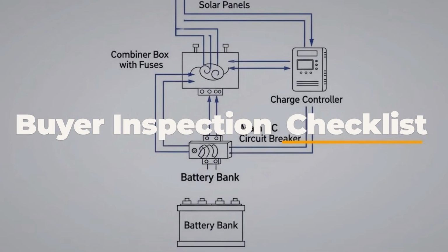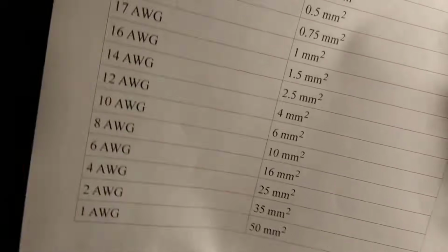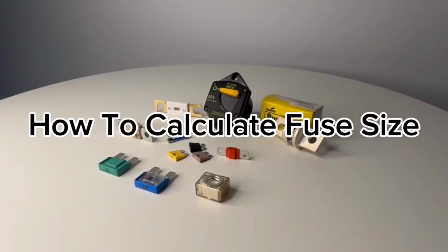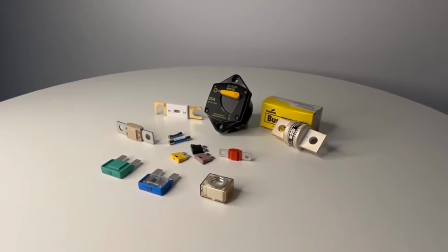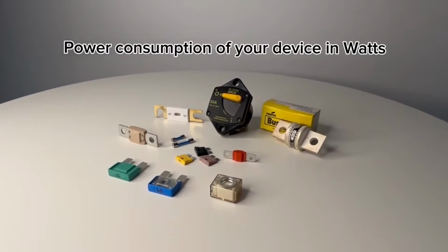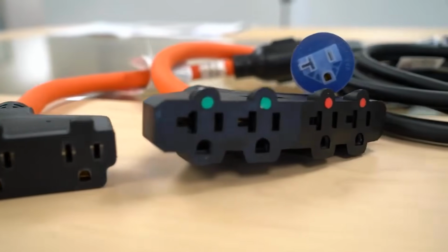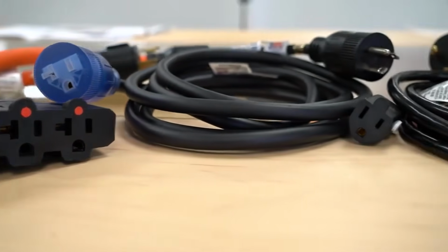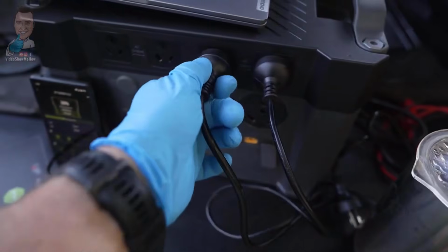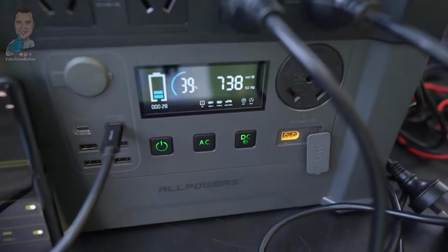The buyer inspection is straightforward. Confirm cable gauge against the inverter's actual current draw, not its marketing label. Measure cable length. Check fuse rating against wire gauge, not just load wattage. Verify each connector's current rating. Count every adapter in the chain. If any one of those numbers is missing from the product listing, the seller does not know their own system well enough for you to trust it under real load.